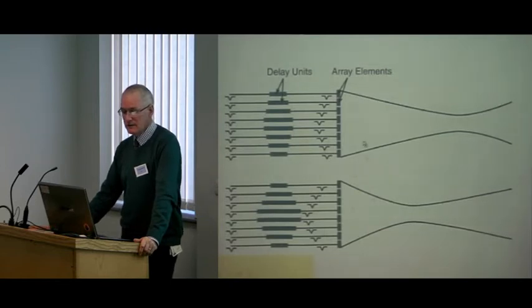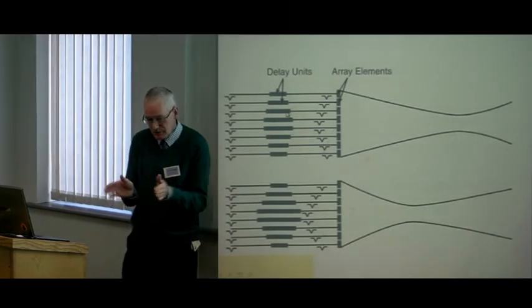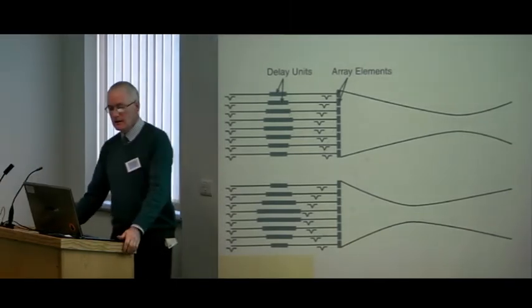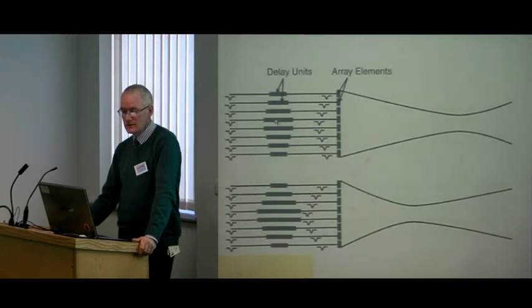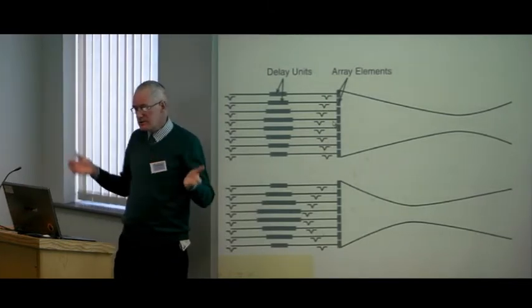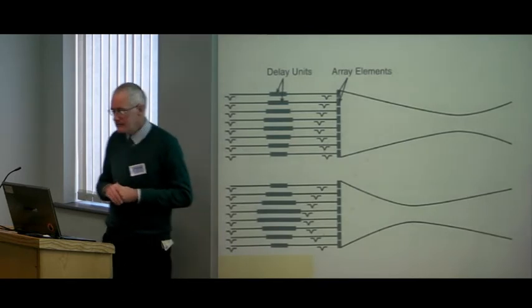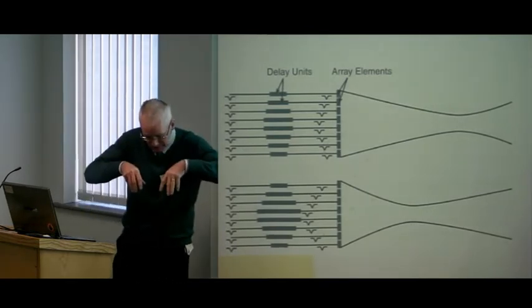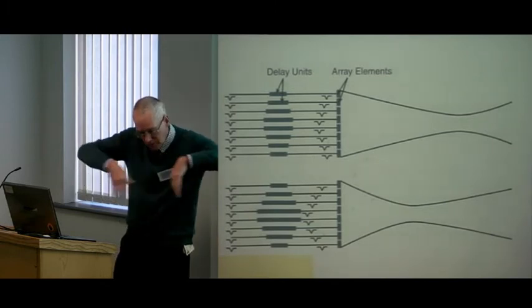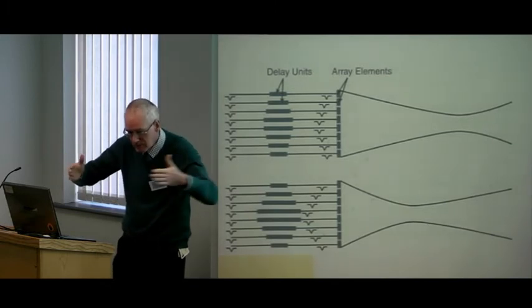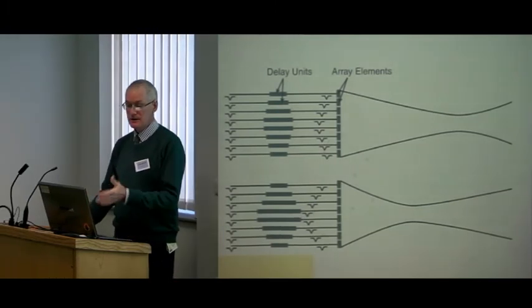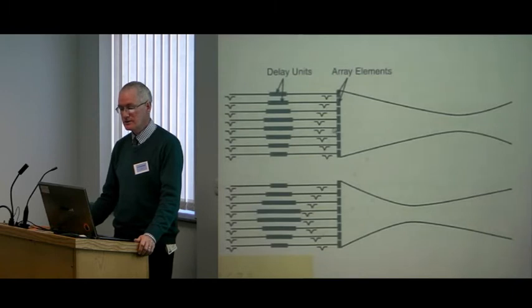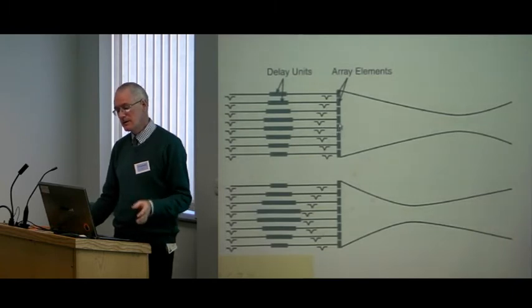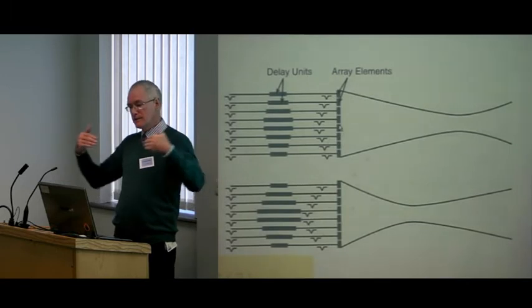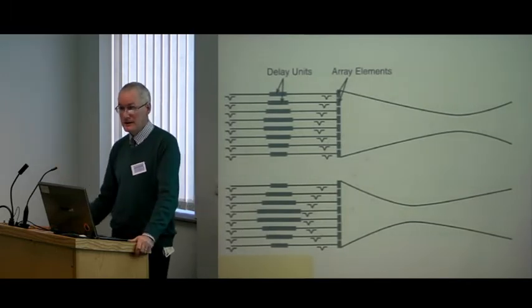This is just basically to illustrate what focus is. The beam has a certain width. You can actually bring the beam to a focus by slowing down some of the electrical current that comes to the middle crystals here. By slowing that down, you bring the wavefronts together, just as you would with pebbles in a lake. If you drop a series of pebbles down, you'll see a wavefront. If you curve those pebbles, you'll see the wavefront will converge. Quite interesting, no? But that's basically using resistors within electrical circuits to slow down the arrival of an electrical current to a crystal, which will then delay the wavefront and focus the actual overall beam and give you better lateral resolution.